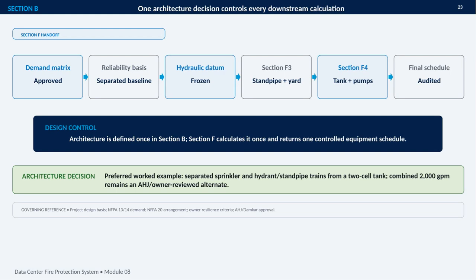The central point is that one architecture decision controls every downstream calculation. Once the architecture is defined, the demand matrix is approved, the reliability basis is separated, and the hydraulic datum is frozen, the later calculations should not quietly redefine the system. The preferred worked example uses separated sprinkler and hydrant or standpipe trains, supplied from a two-cell tank. That arrangement becomes the basis for the Section F3 standpipe and yard calculations, followed by Section F4, which addresses the tank and pumps. The output is a single final equipment schedule, and that schedule is audited before release.